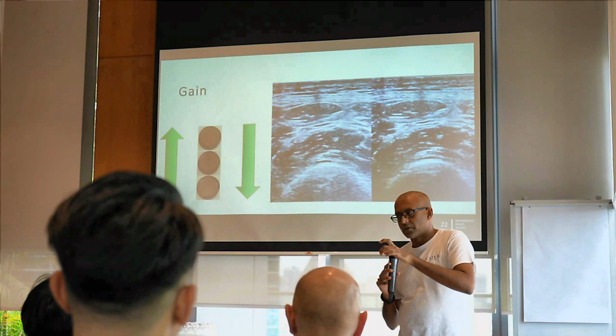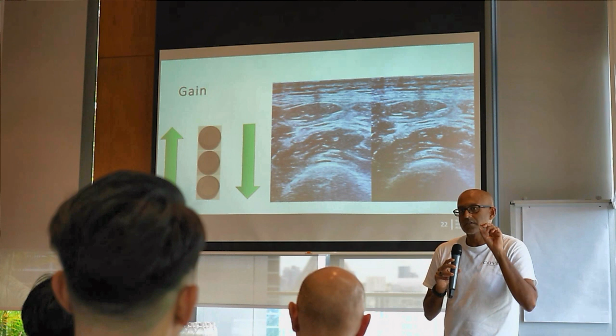But you can see, if you want to see the bone, you need to get that kind of sweet spot where you get enough signal from the deeper structures, but you don't want to get so much signal that it blurs out the superficial structures. Yeah? So adjusting the overall gain is an important step when you're doing your scan. And all of these things you're kind of doing as you're going along. Even if you're scanning the same area, if you change the orientation a little bit, or you adjust the transducer, then you need to adjust it. So it's really like fine-tuning as you go.